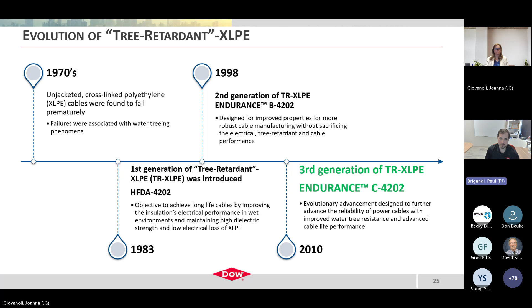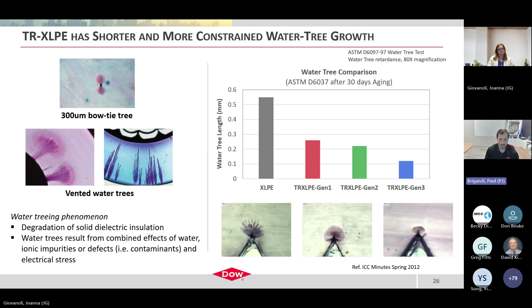This gives you a high level view of the water tree phenomenon. This water tree is something we see within power cables that are in wet environments, whether they be tree retardant XLPEs or EPRs. We've continued to improve the performance of these materials as we've gone from the first generation all the way to the third, and you can see how much it's improved relative to the predecessors, which was just standard XLPE.